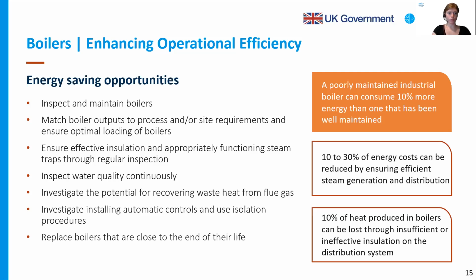So an ideal solution to this would be to have automatic TDS control. This prevents foaming, carryover, boiler water, corrosion of steam and condensate system, while also helping to save boiler fuel. A rule of thumb is that for every 1% reduction in boiler blowdown, you save about 0.2% of fuel. It's a very, very low hanging fruit.